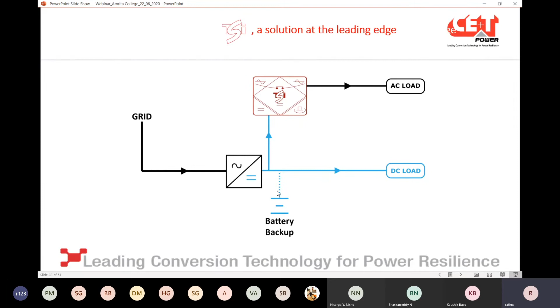When AC is present, you take directly from the grid and convert AC to DC, with each module inside the TSI having a static switch implemented. It's hot swappable and hot redundant, so you can easily unplug a module and plug in a new one in case of failure. Since we use the existing DC, when AC is not present, you take the DC and convert it to AC, and still supply the AC load.